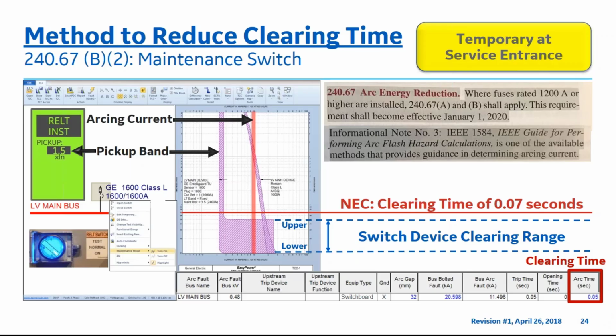voltage power distribution section. Please notice that the clearing time represented in the beginning portion of this presentation had a diagonal green line drawn at 0.05 seconds, or 50 milliseconds, per the IEEE 1584-2002 arc flash equations in the arc flash instant energy analysis slide.